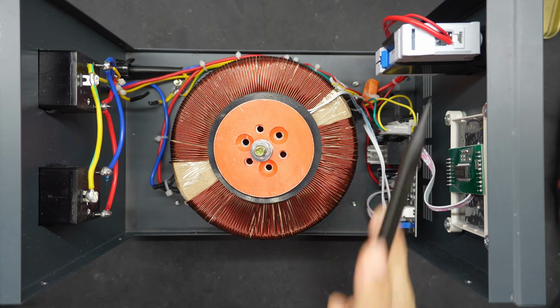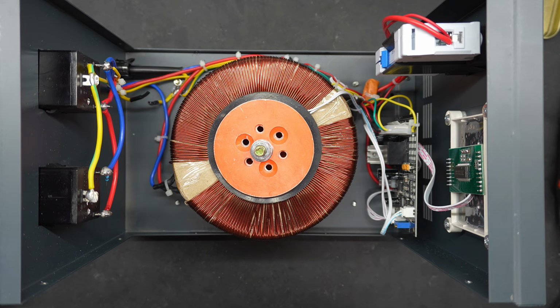Starting with the fuse here - this is a special type of electrical fuse, I'll pop up a picture for you to see it. It's got a built-in fuse. This switch is rated, I believe, for 10 amps, and anything above that it'll trip. Now the issue is, with the 240 volt supply, this transformer can really only take about 4 amps. If it was a 120 volt supply, it would take 8 amps.